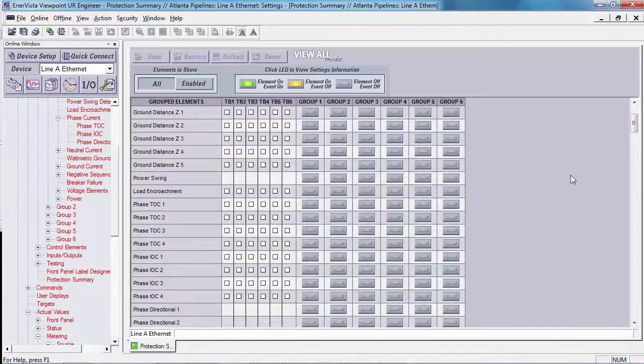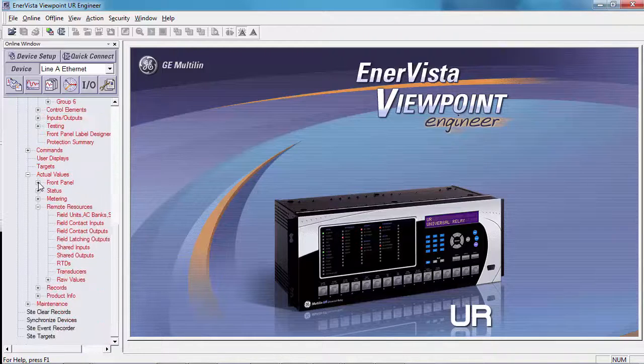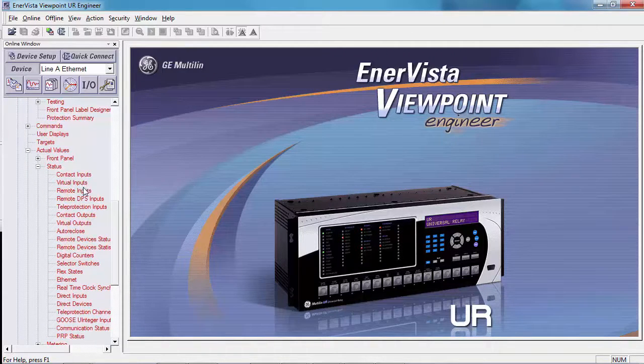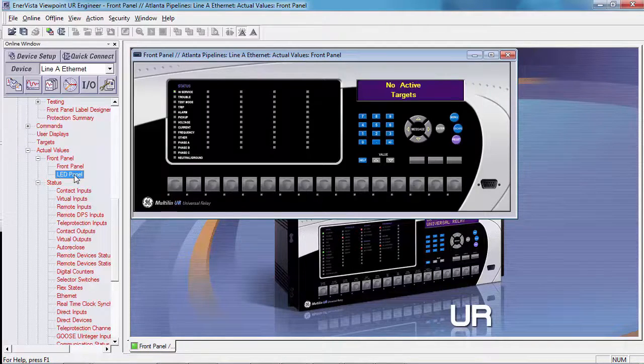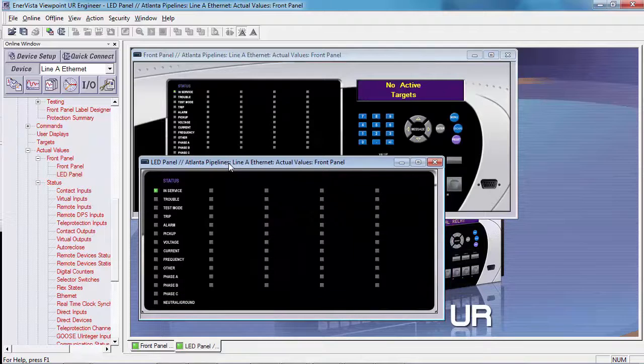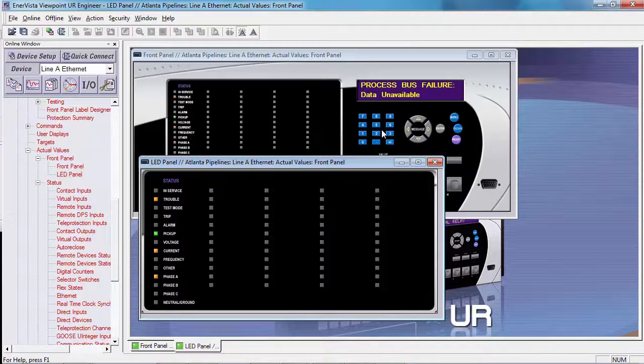So now we come back to the screen, the IOC is enabled, and let's just do a quick verification. I'll go to the front panel so we can see what's going on. And again, we'll increase the current. And we see the same type of configuration. Okay, it operates the same way as the DSP card.